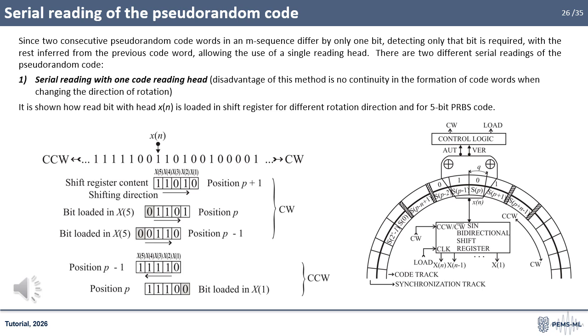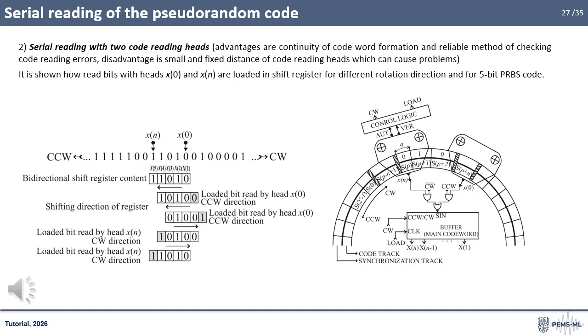There are 2 different serial readings of the pseudorandom code. Serial reading with 1 code reading head has the disadvantage of no continuity in the formation of code words when changing the direction of rotation. It is shown how a read bit is loaded in the shift register for different rotation directions and for a 5-bit pseudorandom code. Serial reading with 2 code reading heads has advantages in continuity of code word formation, and it is a reliable method of checking code reading errors. The disadvantage is the small and fixed distance between the code reading heads, which can cause problems. It is shown how read bits are loaded in a shift register for different rotation directions and for a 5-bit pseudorandom code.